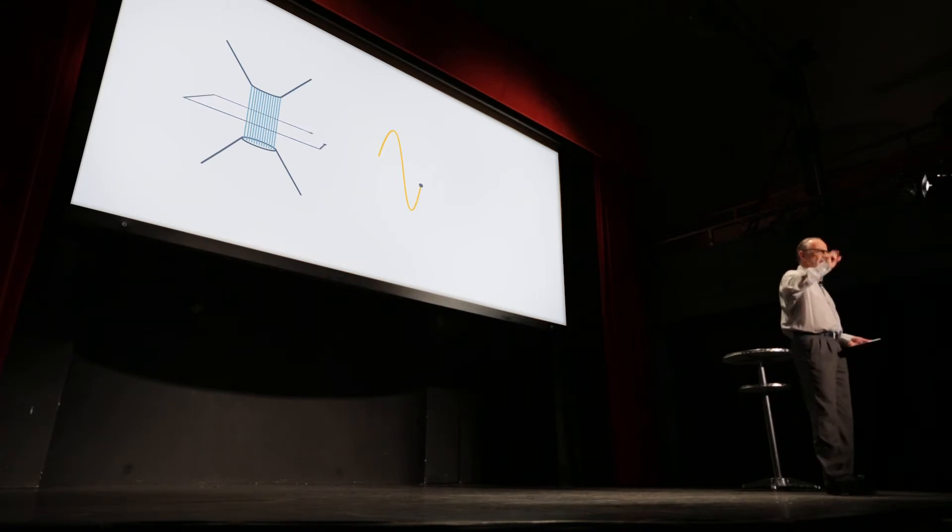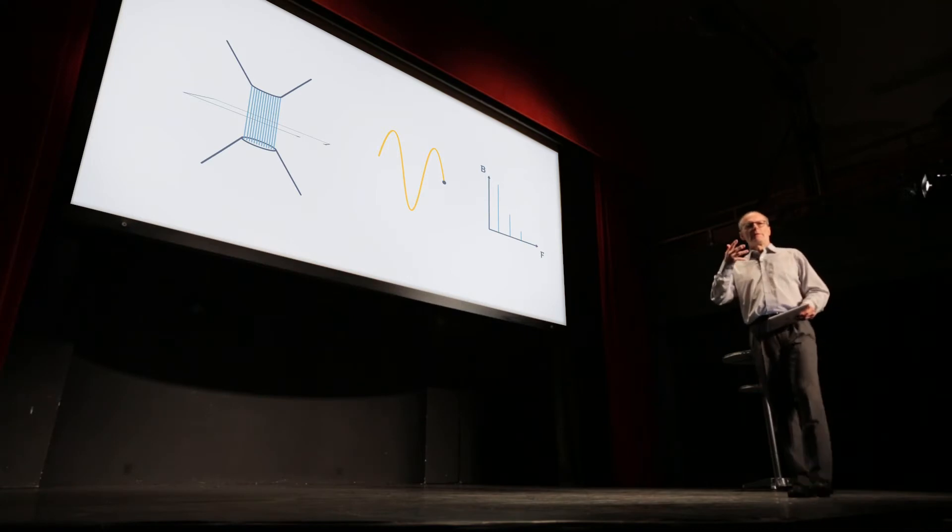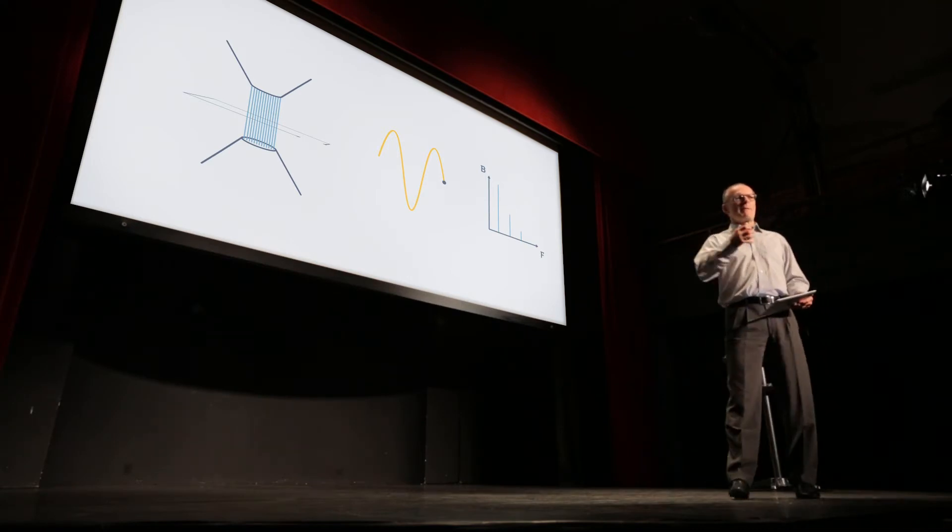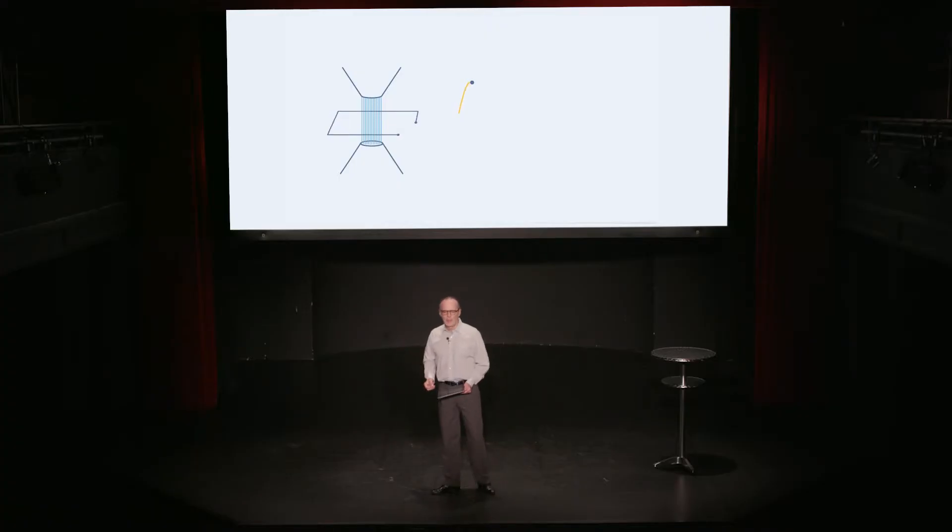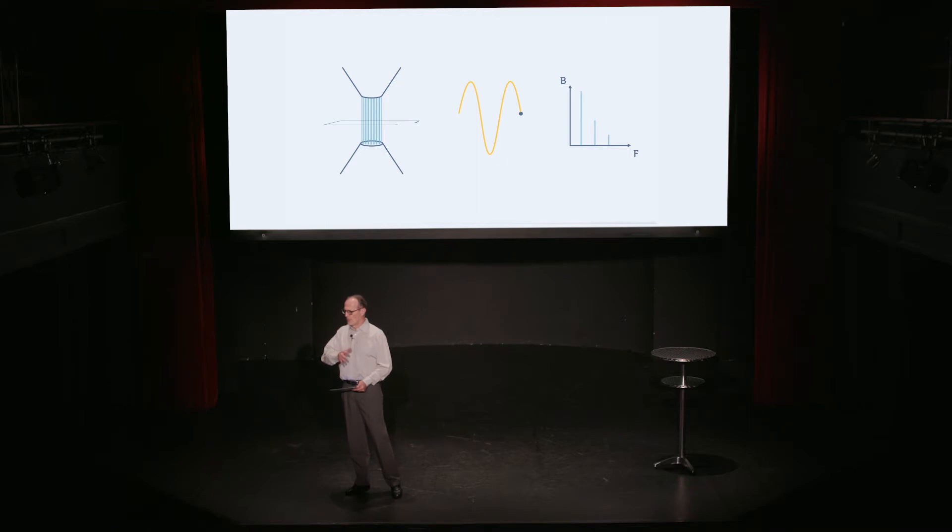By taking a Fourier transform of these measurements, we calculate a multipole model for this particular magnet. The first order one, which is just the sine wave, is the dipole component. How does this magnet bend the beam? The second component is the quadrupole moment, which tells us how this magnet focuses the beam, and so forth. Often, scientists measure up to 17th, 18th order to be able to include all the effects that this magnet will have on the beam.